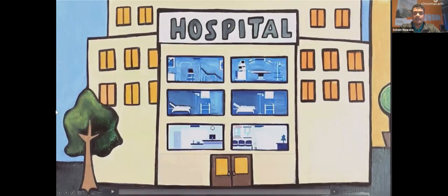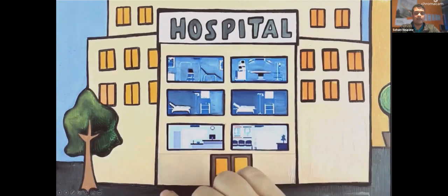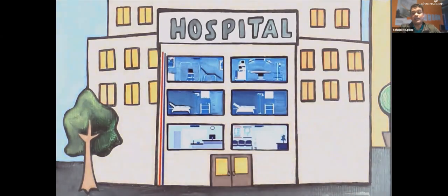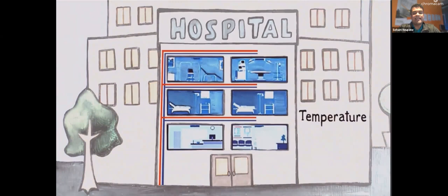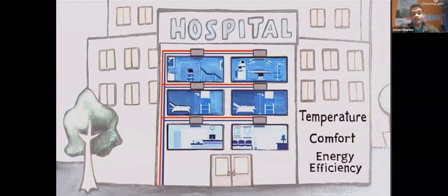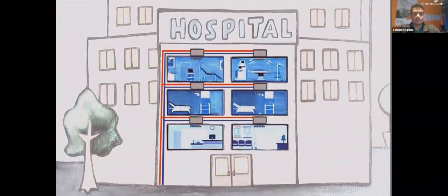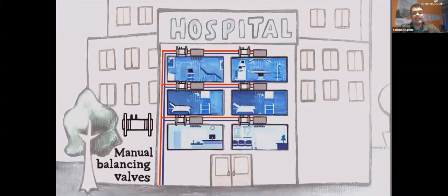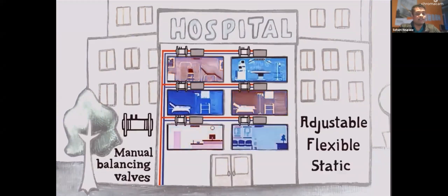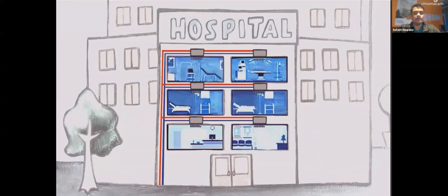So let's look at this quick clip here on manual balancing. So any building, we've got your supply, you've got your return, and that connects to your heat exchanging device, right? Your coil for your comfort to each room. And it could be balanced using manual balancing valves. So you'd have manual balancing valve on all the terminals. And those valves are adjustable and flexible, but it's static. So when I say adjustable manual balancing valve, it can be set for different flow, because you have a handle that can adjust for different flow. So it has a range it can control.